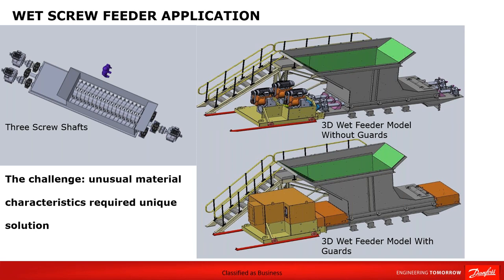So as I said, should any of the shafts go out of sync, even by a programmable limit, the machine must come to a stop. What do I mean by that? Well, for example, if one of the motors, gearboxes or shafts became overloaded and slowed the motor down, it had to be detected by an out of synchronization function, and all the screw shafts had to stop. And once the problem had been cleared and the application had been brought back manually, the application had to revert back into the correct synchronized position automatically when started, instead of having to return the shaft to a home position manually. Now, during normal operation, the load on each drive is relatively light, at less than 50% of motor full load torque. But because of that material's consistency, there are times that we found when higher loads occur.